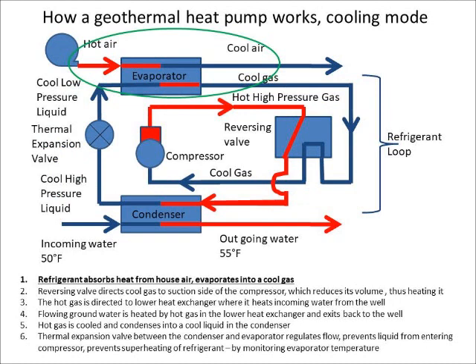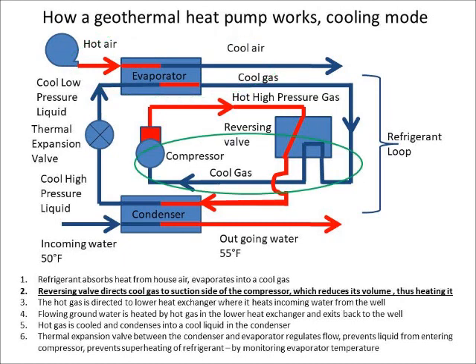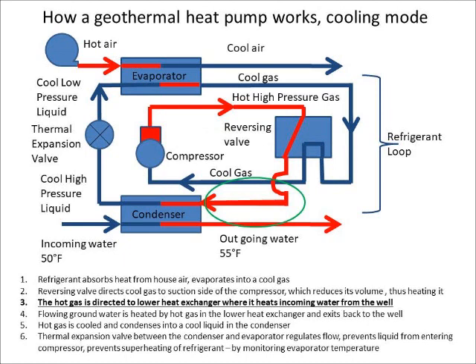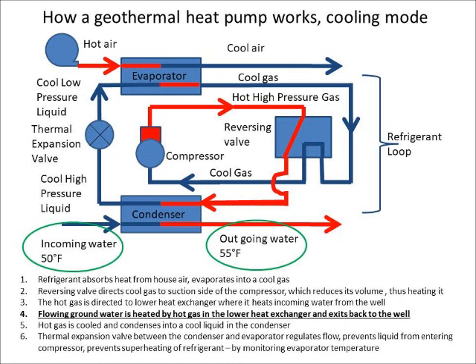This is a more detailed view of the geothermal heat pump in the cooling mode. First, the refrigerant absorbs heat from the house air and evaporates into a cool gas in the upper heat exchanger. Second, the reversing valve directs the cool gas to the suction side of the compressor, which again reduces its volume and heats it. Third, the hot gas is directed to the lower heat exchanger, where it heats incoming water from the well. The flowing groundwater is heated by the hot gas in the lower heat exchanger and exits back to the well.